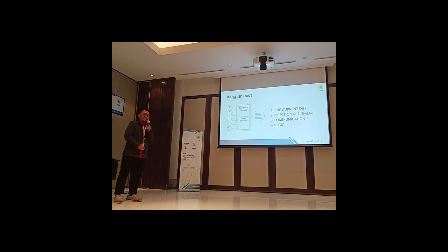Let's go back to my first tagline, the IED, or intelligent electronic device. We have intelligence; we have everything inside this. Inside the line current differential relay, we have the line current differential function itself, but besides that we also have directional elements, communication, IEC 61850, and logic that we can modify as much as we want.